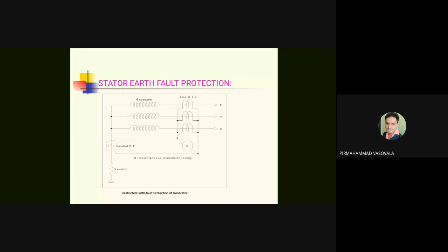But just to introduce stator earth fault protection, you can see on your screen restricted earth fault protection, REF, or differential protection. There is one CT in the neutral circuit and three CTs in the line. The relay is connected as you see. This is current based protection, used when the neutral is connected through resistance. As we have discussed, the neutral has to be connected with an intentional resistance in the circuit, because otherwise the current will be so large that the stator will be badly damaged.